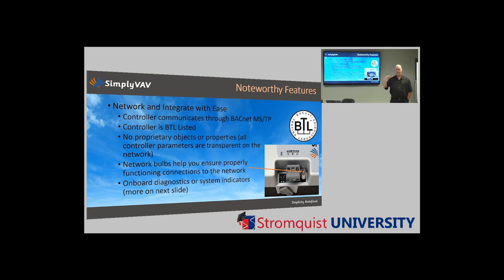They take your product, they test it for the BACnet standard you have submitted it for, and if it passes that test, it gets to bear the BTL Testing Laboratory stamp. If you go to BTL's website, you can look up by manufacturer and open their page and see all of the various products that they have listed that they have put through the BTL testing. It costs a little bit of money to do that, but we believe in the end it's worth it from a credibility perspective. There are no proprietary objects in our network.